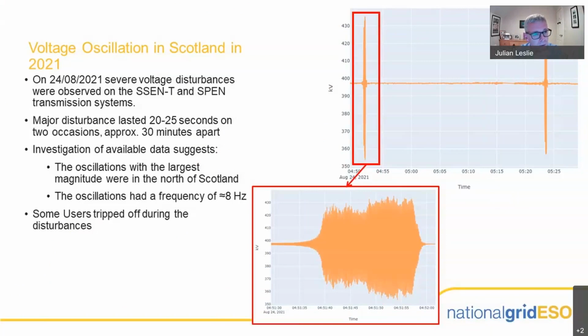And we saw some quite severe voltage oscillations on the network, which seemed to be about 30 minutes apart and lasted for 20-25 seconds. These oscillations had a frequency of about 8 hertz, and I think about 14 kilovolts in terms of magnitude. Actually, the graph shows a bit higher than that, plus or minus 30 kilovolts from where it was at the starting point.